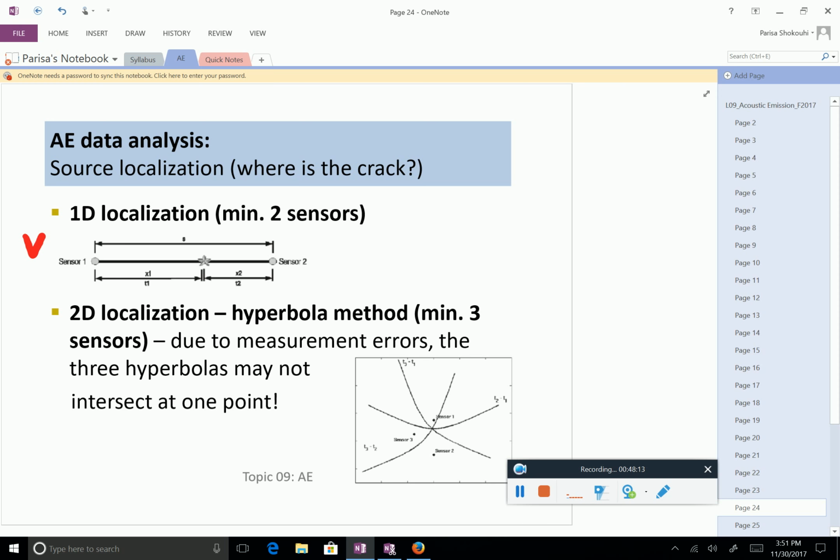There is something everyone is missing. We know the velocity. I'm sorry, this is a very important point, but I assume that you know the velocity. If you don't know the velocity, it becomes complicated. Exactly. Then we would only need one transducer, but I'm saying we need two.